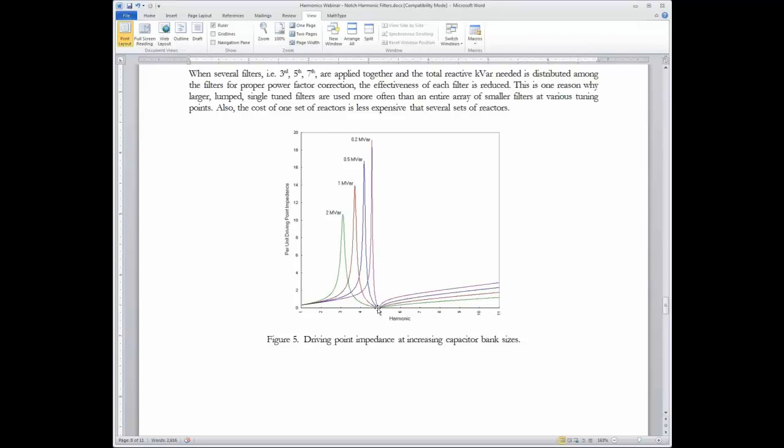There's a ton more details that I could say on that about how you have to make sure that you also include things like blown can protection. I just didn't have time to put that in here. So we've looked at slightly detuning the filter for this first parallel resonant point. We looked at how it changes.